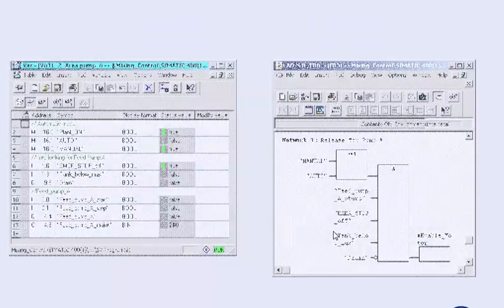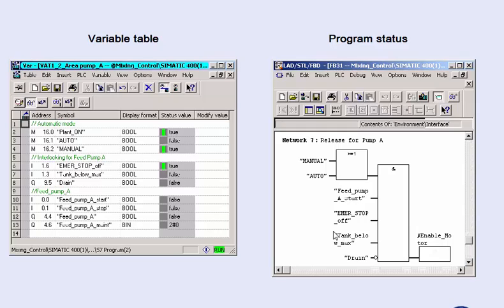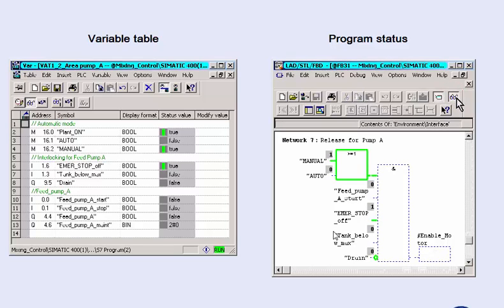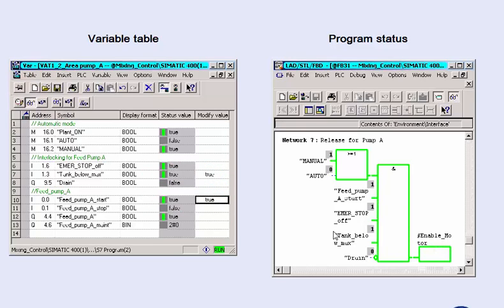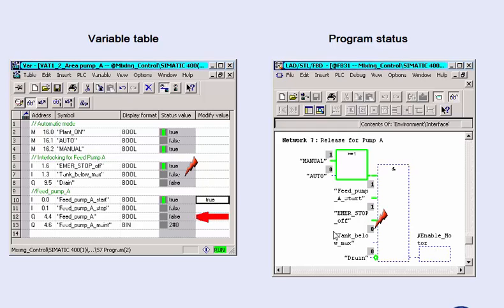An example will now show you how to combine the test functions variable table and program status in order to achieve the optimal overview in the testing phase. We activate the program status, which shows us the logic operation for operating a pump, and control the switch on via the variable table. The effects can be immediately observed in the program status. The pump output is activated. If, against all expectations, the pump switch is off, the missing conditions can be immediately recognized in the colorized signal flow.